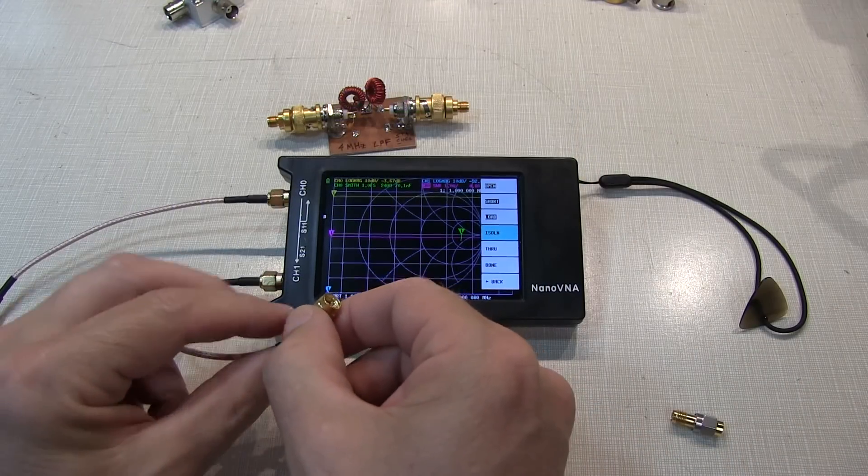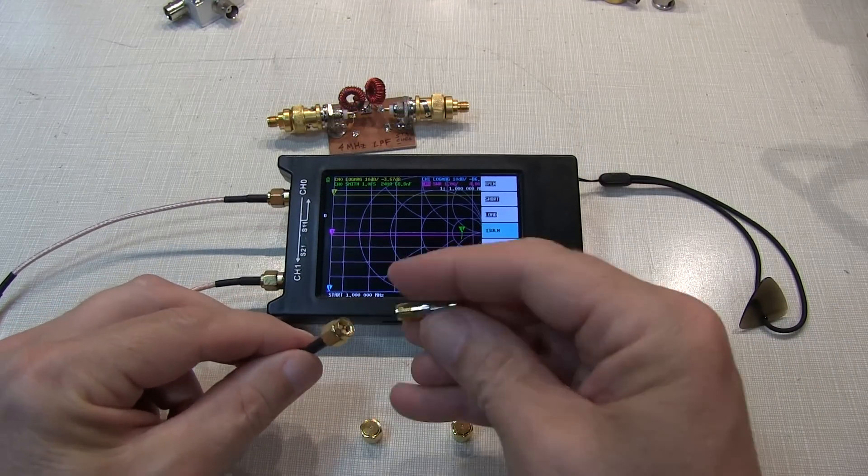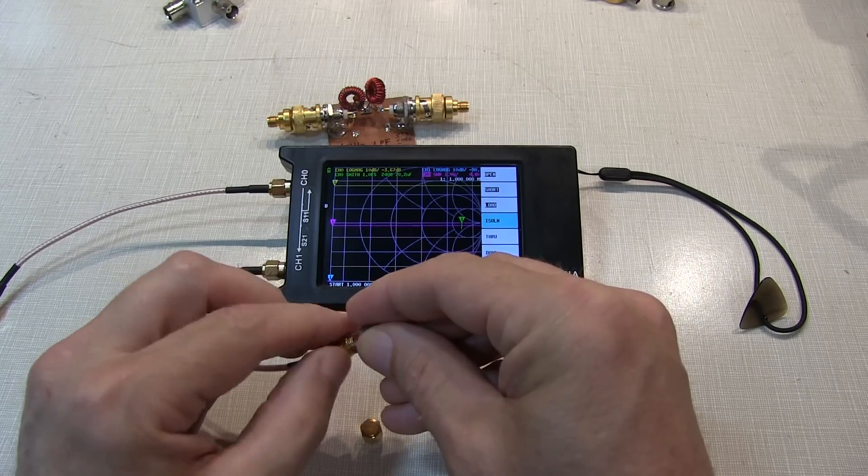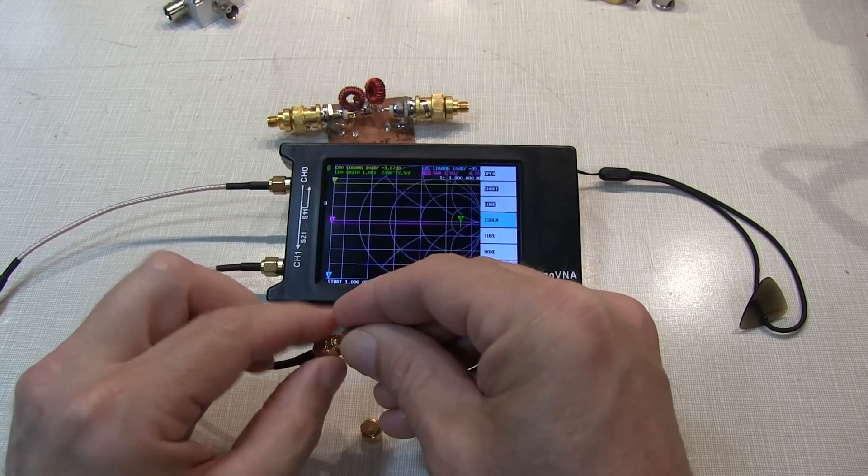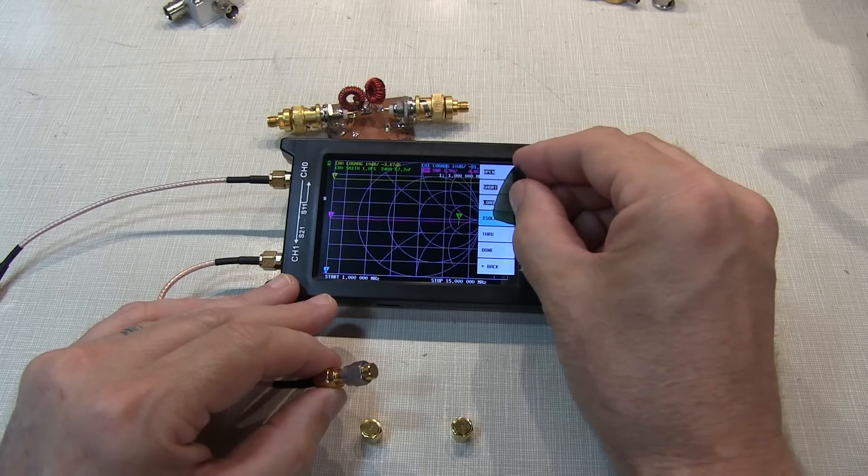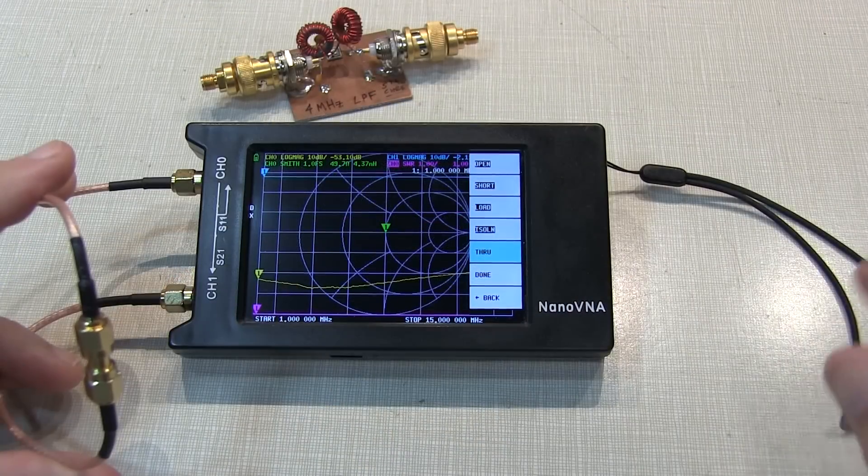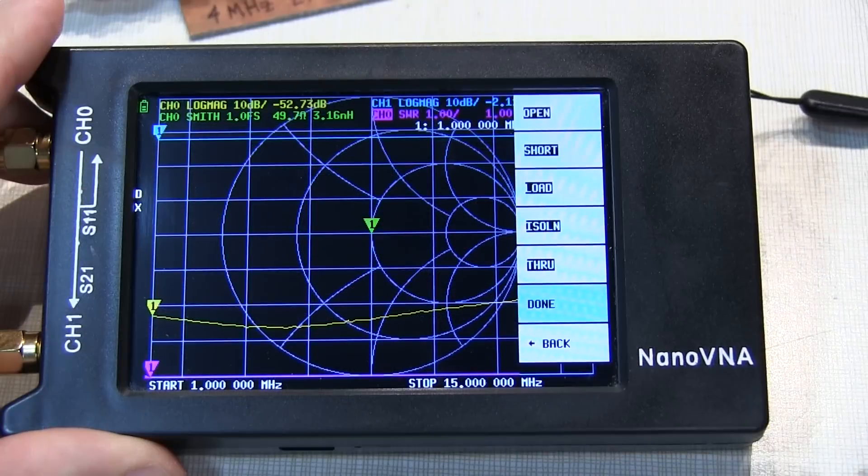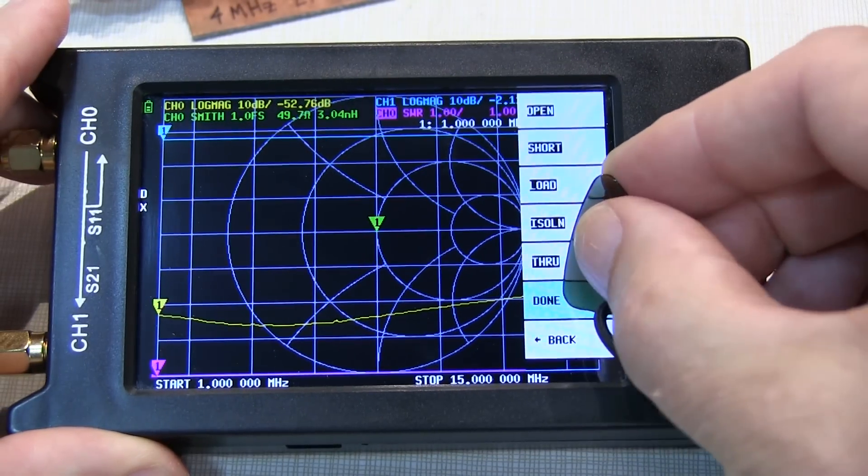Now for the isolation measurement, it's a good idea to terminate channel 1, or the input port, so I'm taking that 50 ohm load and the bullet and connecting it to the cable that's connected to channel 1, and then we can hit Isolation. And, of course, connect both cables together to do the through calibration. With all the calibrations done, we can hit Done.